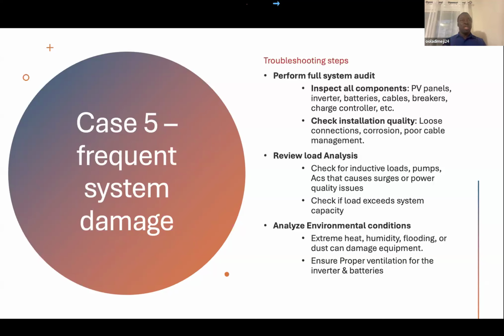Then check installation quality. Have you used the right cable sizing? Are there loose connections, corrosion, or poor cable management? Poor cable management can be a headache because I've seen an installation without color coding, where the earthing, the power cable, the load cable, the neutral, everything used a red cable. So there is no way to know which one is which, and that's a headache already.